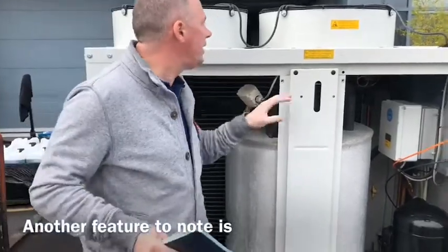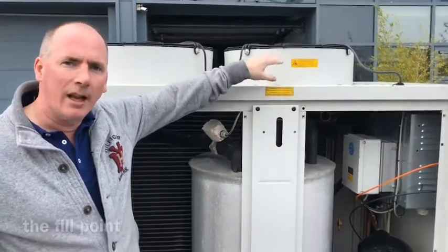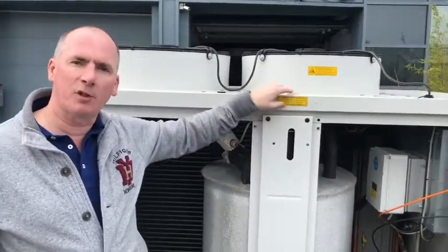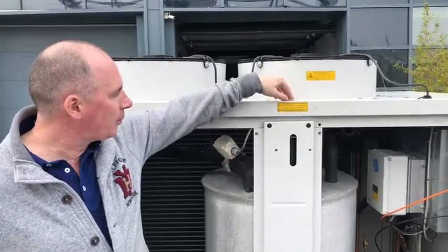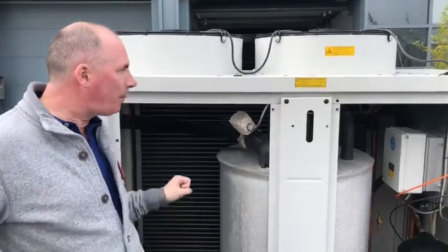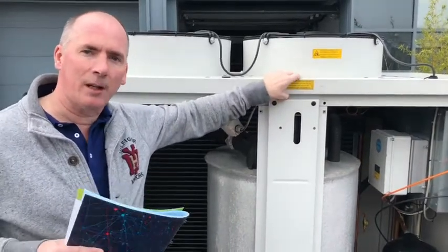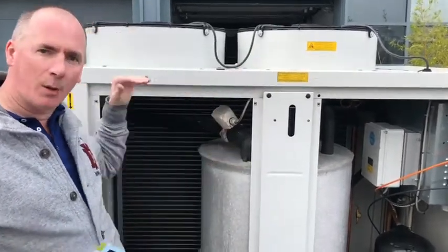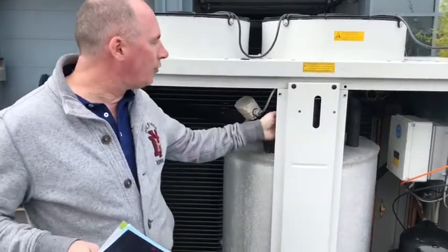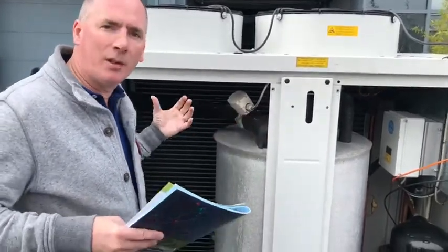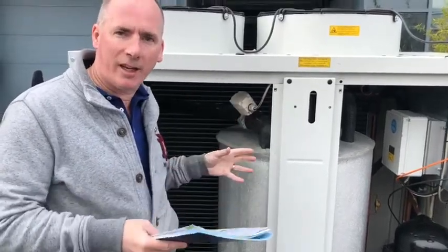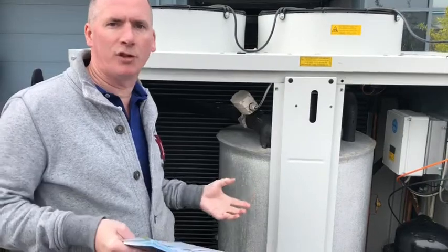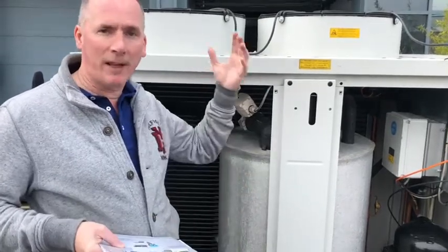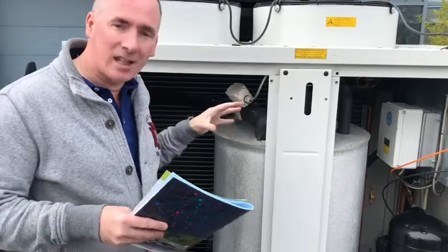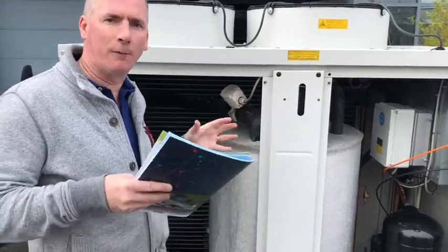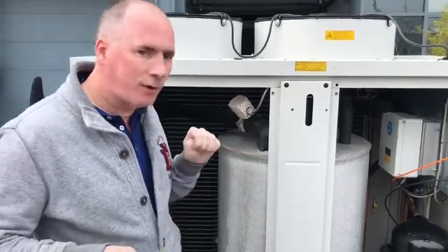The other thing of note is these come with a fill point. So again, you can literally land them beside the machine to be cooled, fill it up with your water here, start your pump, the level will drop, top it up again, and away you go. So they're very, very plug and play. Now, that being said, if your pipework is at a higher level than the chiller, we would recommend you seal off the fill point and then install an expansion kit, which is basically an auto-filling valve, or of course you can use a pressurization unit to fill. You should have vents at the high points and an expansion vessel, which is typically sized based upon the volume in your system. So I'll just show you around here.